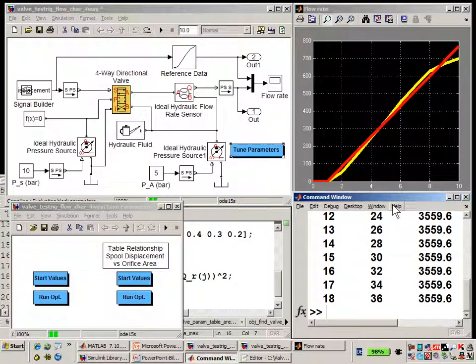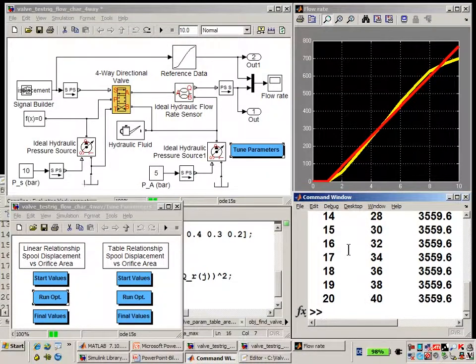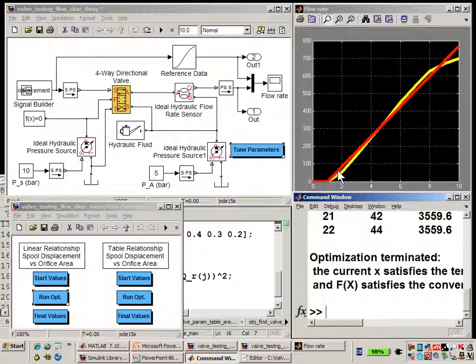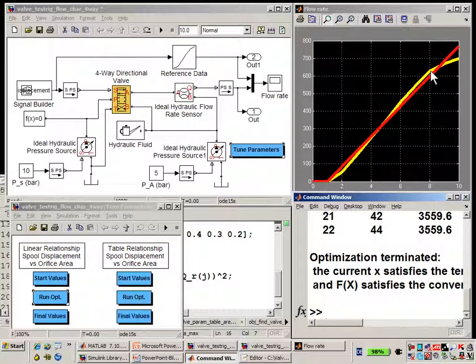At the conclusion of the optimization, we'll see what the results are. The optimization is complete — this is the best value of A_max that makes the two curves as close as possible. We can see it's much better than where we began, however there are still some differences between the curves. The reason is the parameterization option we've chosen: the first option results in a linear relationship between the control signal and the area, which directly affects flow rate. This is probably valid between 0 and 80%, but if we want the simulation to match more closely, we'll need to select a different parameterization option.